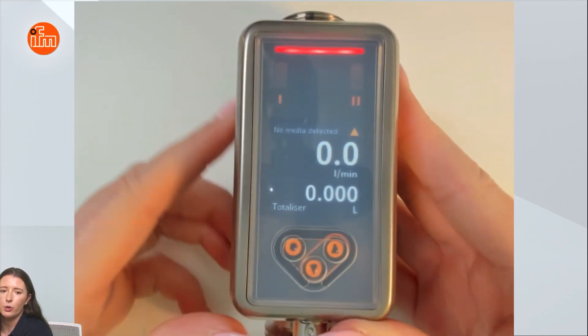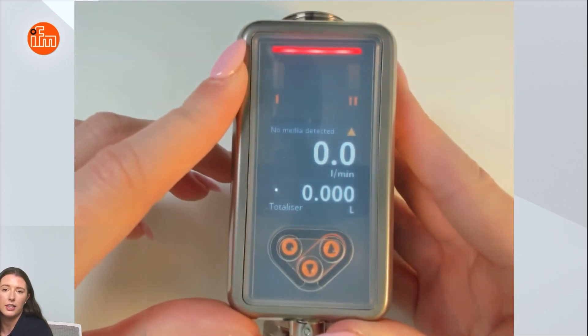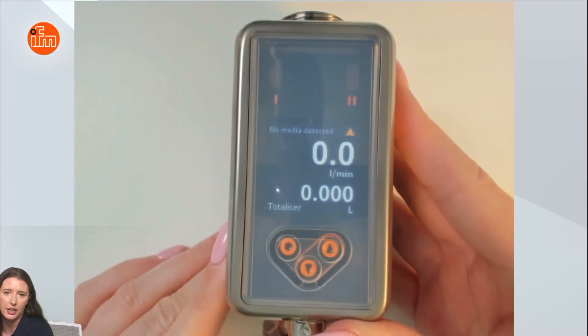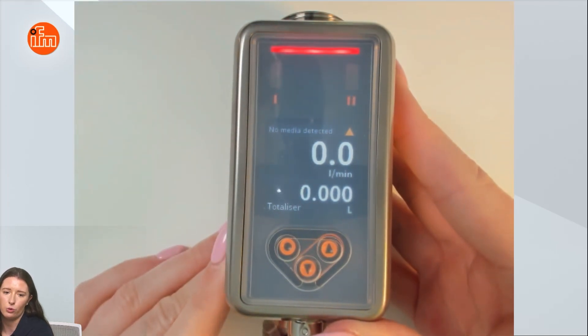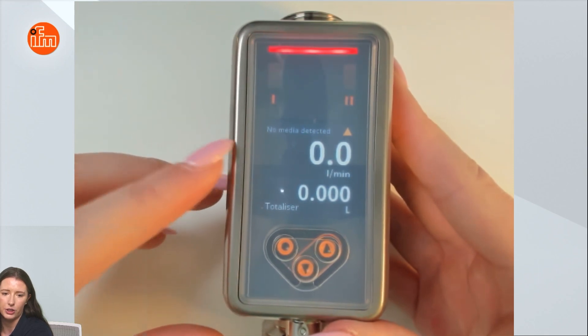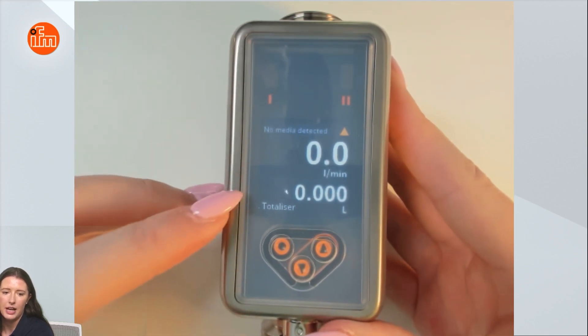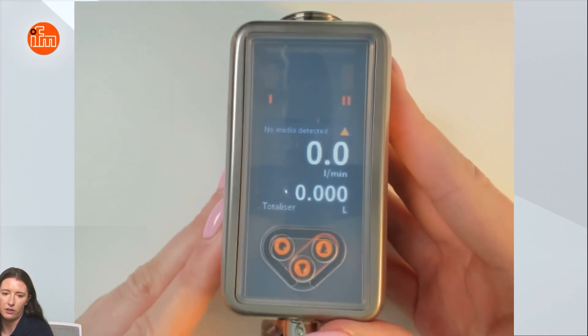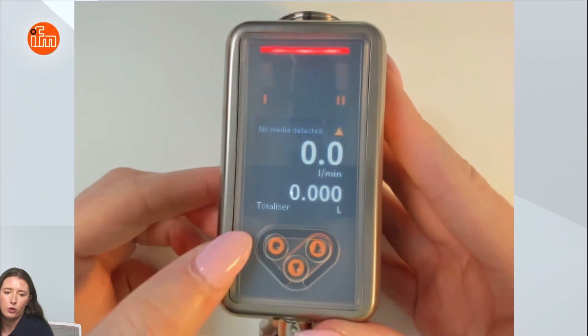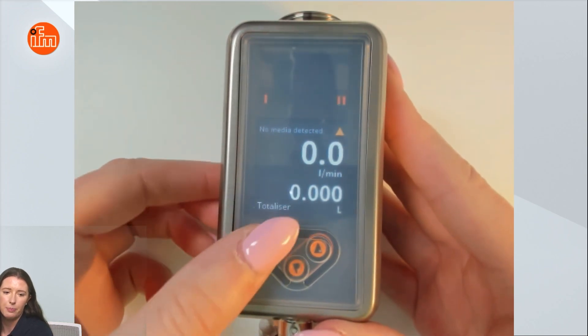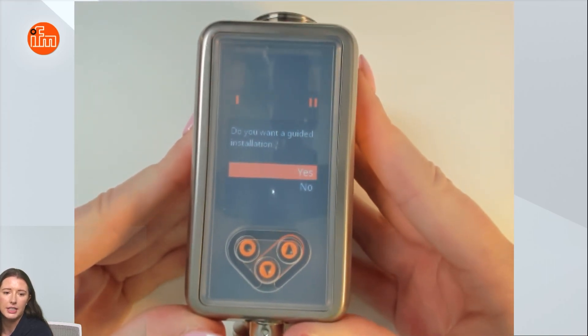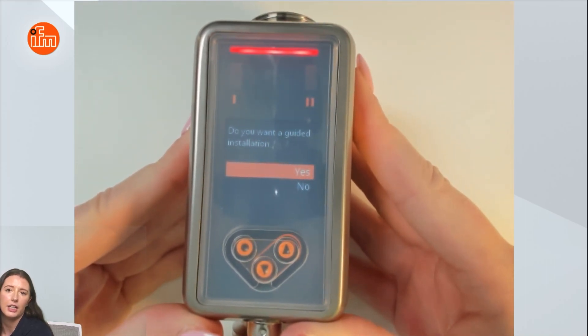In this example you are going to see the signal quality LED flashing red because we do not currently have any media passing through the sensor itself. Here you can see we have the flow rate set for liters per minute and the totalized value set for liters out of the box. Now if you want to go into the menu you'll press this enter button, and out of the box the first thing you will see is this guided installation wizard.